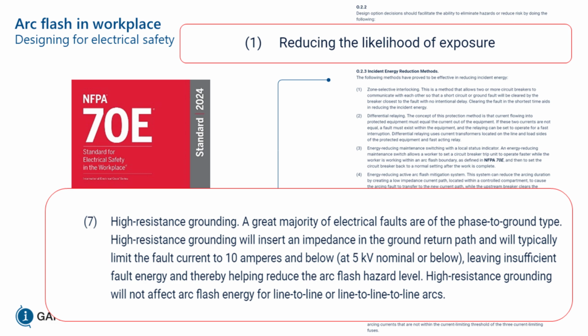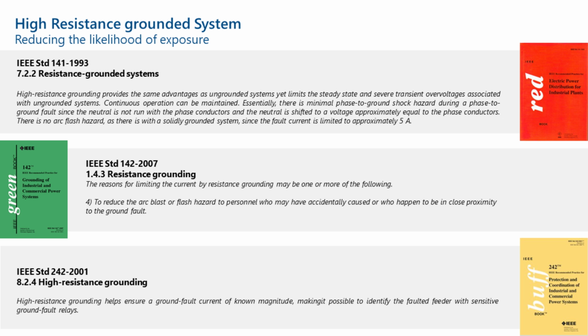So what does NFPA 70E say? High resistance grounding is an arc flash mitigation technique. It reduces the likelihood of exposure. If you look at all the other incident energy reduction methods, they limit the severity of exposure, but this is one of the only techniques that limits the probability of having an arc flash at all. So this is working before you have an arc flash. Everything else is working after you get an arc flash to minimize the time that the fault is on the system. So both NFPA 70E and Z462 say that high resistance grounding is an arc flash mitigation technique because it reduces the likelihood of exposure. And the Red Book, the Green Book, and the Buff Book all say the same thing.